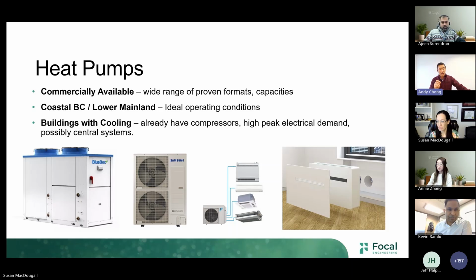There are changing refrigerant technologies, different operating temperature regimes, different space and maintenance requirements. Are we bolting these on the side of buildings, putting them on the roof? It's a different space requirement than we're used to when we buried a piece of gas equipment in a boiler room in the basement or a penthouse on the roof. These things often need access to outside. They're not immensely heavy, but they don't weigh nothing, so we need to tell our structural friends about them.